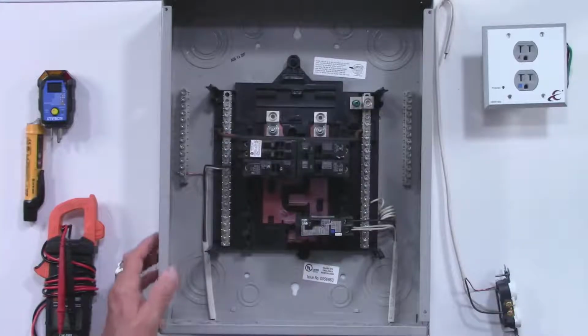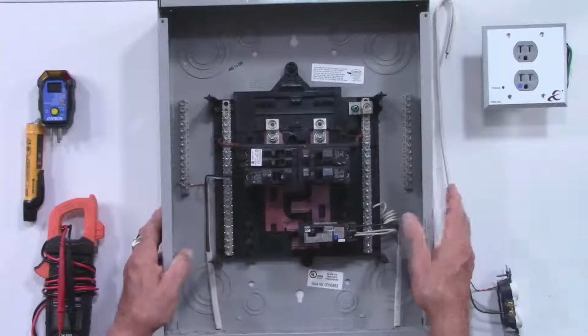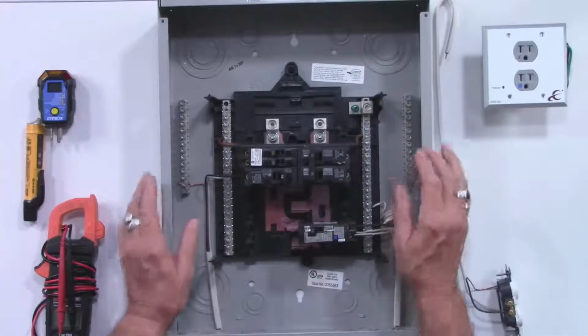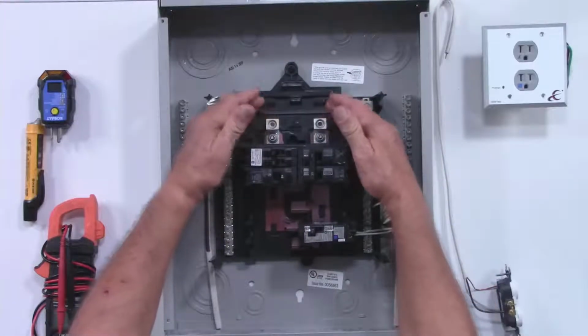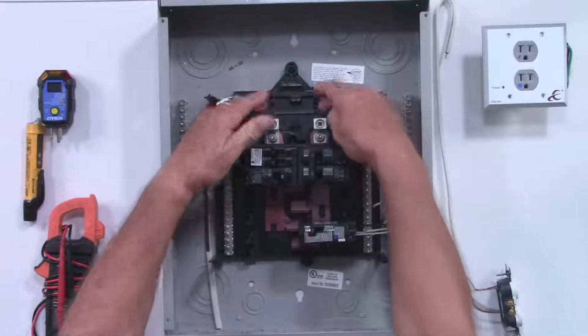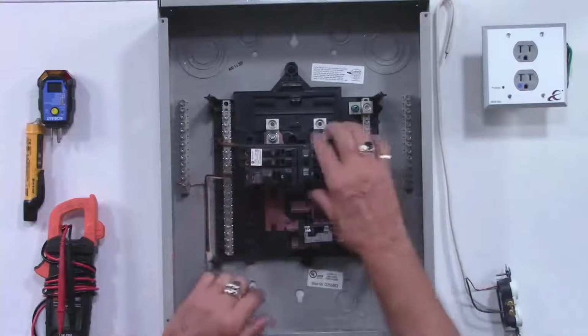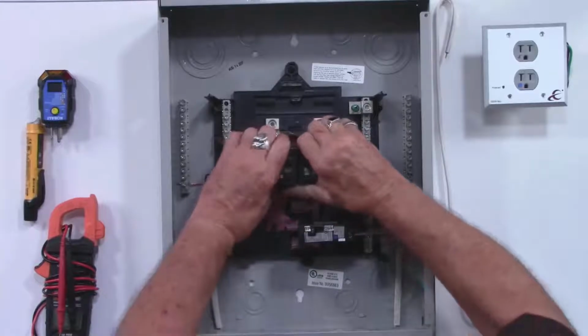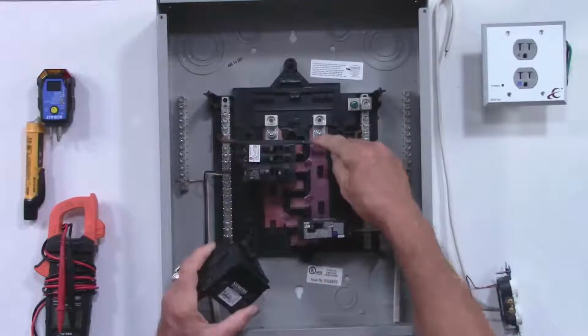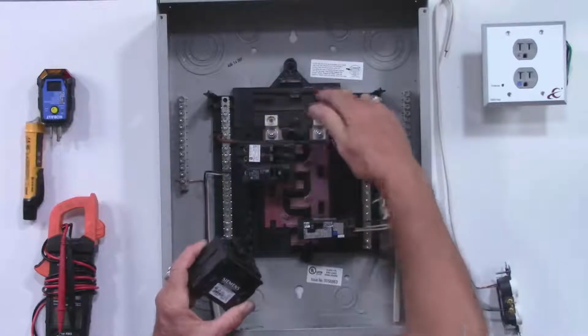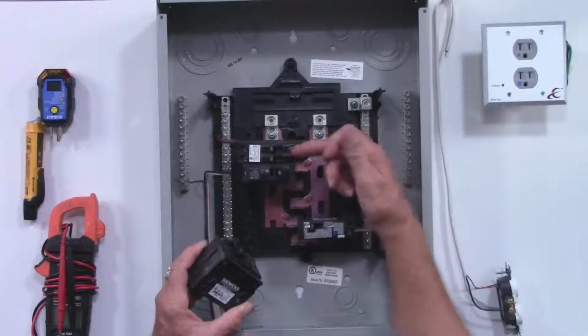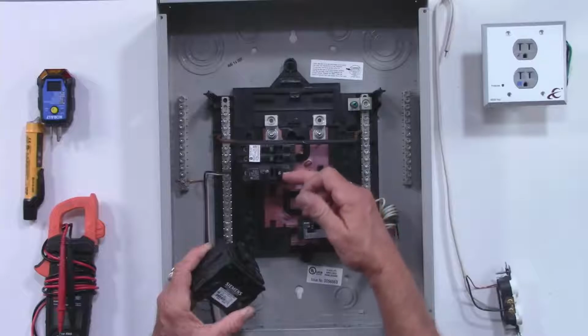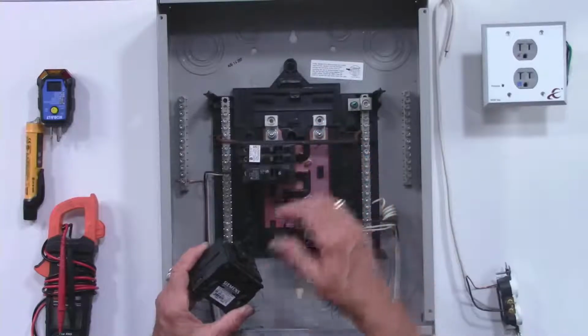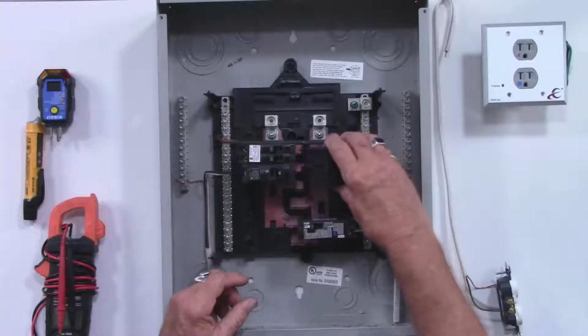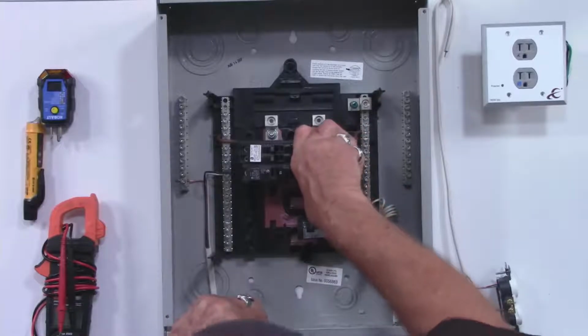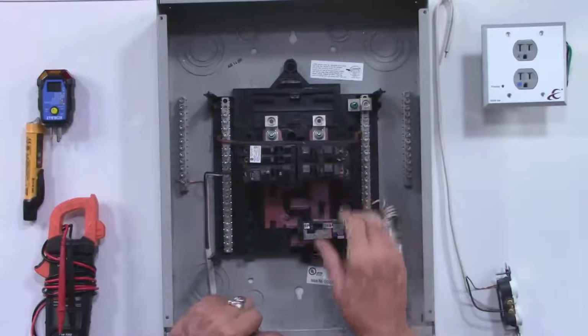Okay, typically a panel, and we all know we use 110 volts, 120 volts as you would call it. And in a panel we have 220. They come in on each side, 110, 110 here, and that makes a 220 across the buses. The buses are staggered. We call them A phase and B phase. So we have A phase, the second row down will be B phase. Then between the two, that's how we get our 220. So it's not left and right, it's alternating up and down. First line, second line, third line, fourth line. That is correct.